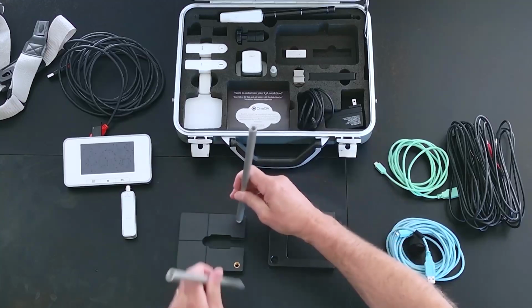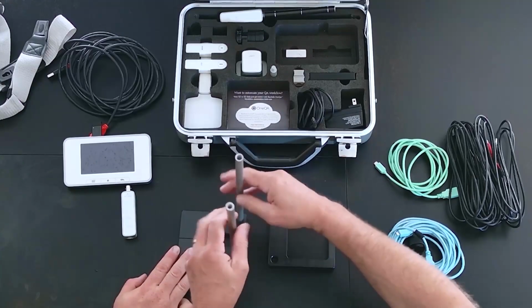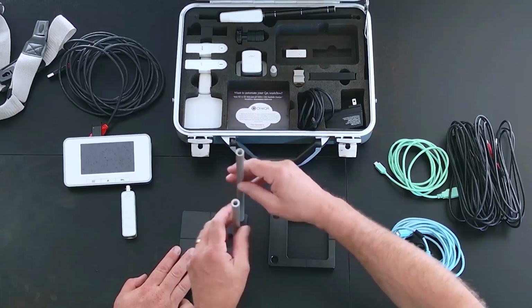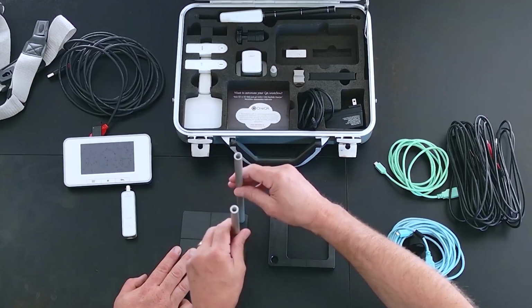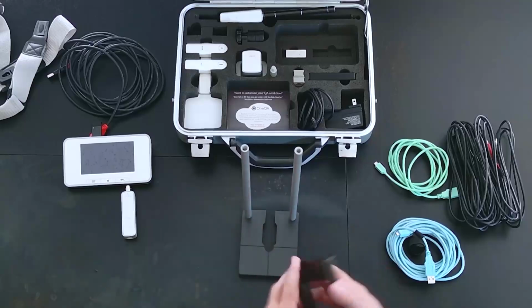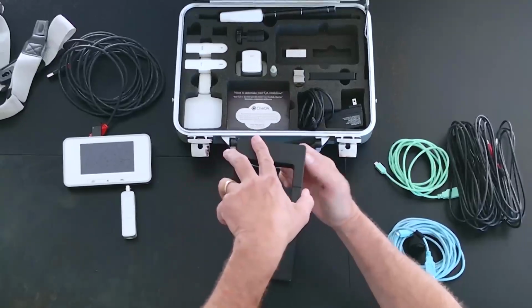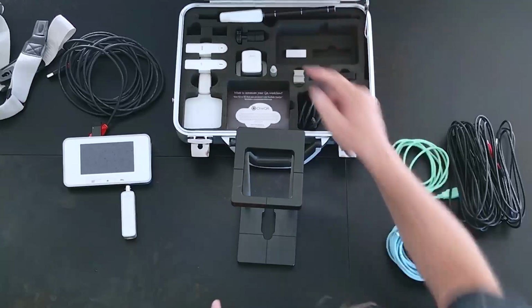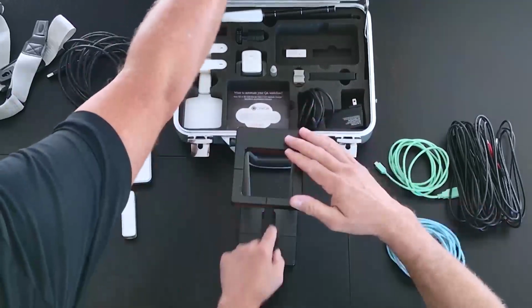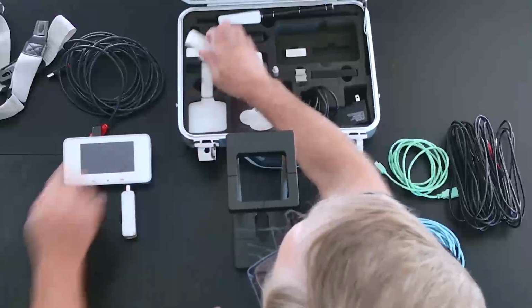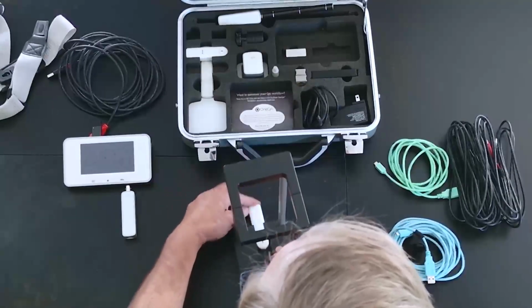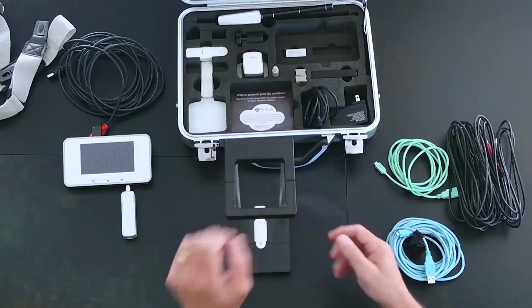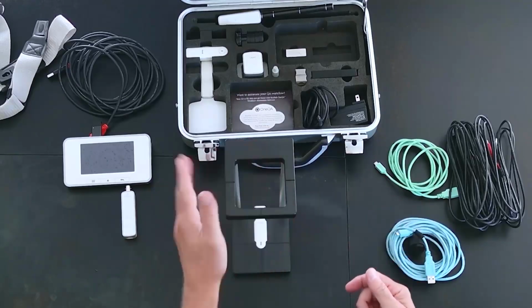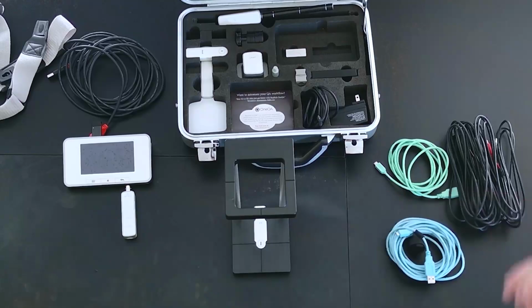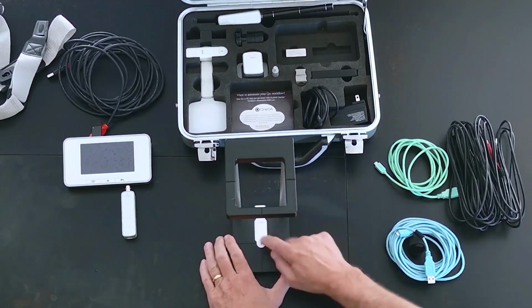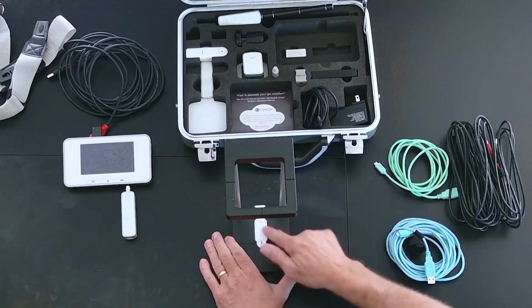So originally the flexi stand, in a previous iteration, actually for one of our earlier models that couldn't measure HVL automatically, we had it configured as an HVL stand. And you know that piece of aluminum that I just put up there, we'd put that on top. So we would make an exposure with the RF sensor, for example, and then an unfiltered exposure, and then we would put the aluminum on top, make another exposure, record the dose, make another exposure with more aluminum, and manually calculate the HVL. We don't do that anymore because the HVL is automatically calculated in the RF sensor.